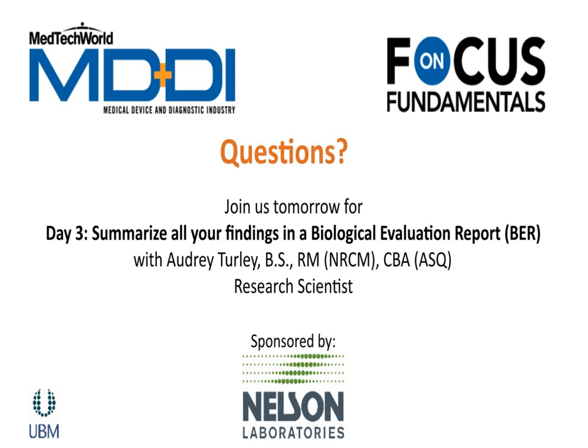Great. So our next question is, to understand the risks to the patient, would a clinician familiar with the device procedure be consulted in addition to the toxicologist? It's going to depend on whether a clinician needs to be involved. Generally, a toxicological evaluation is done by the toxicologist. If we find that there is some sort of clinical aspect that needs to be considered, that would be something else that needs to be submitted by the clinician. What we are evaluating as toxicologists is whether the exposures to the chemicals are safe.